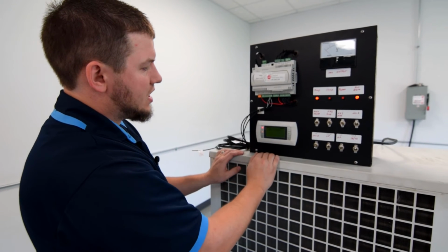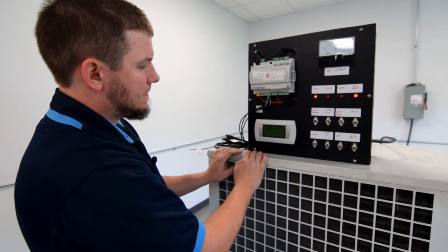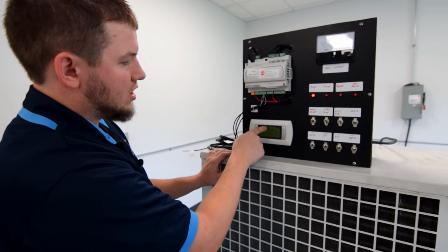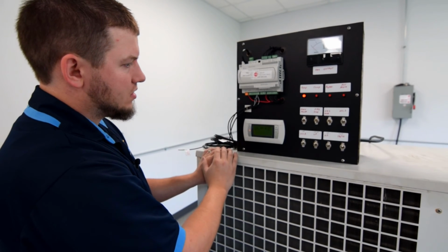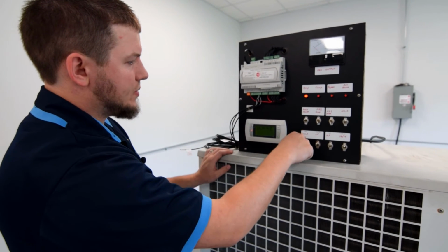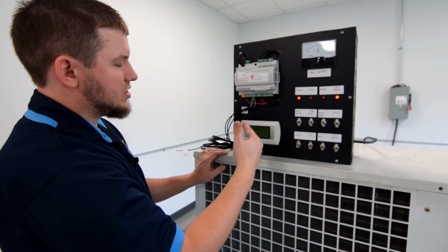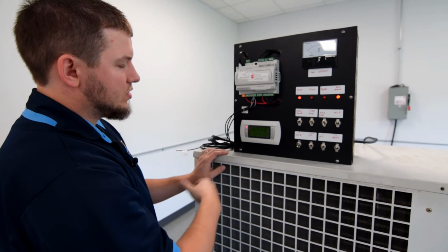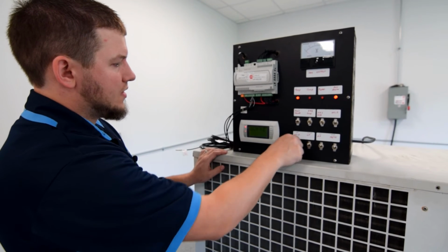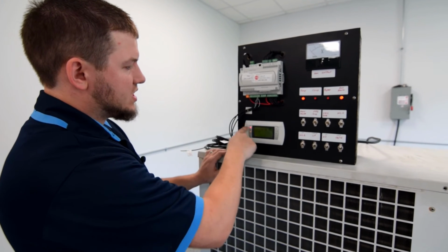Okay, so let's say that this alarm has been corrected. It's still going to show it here, but if you hit that button, it's going to erase it, as it obviously did. Now what happens if this same alarm happens again? This is a high pressure. So let's say the compressor turns on, it hits a high pressure state and it shuts off. You reset it, and the alarm goes back, and you reset it.